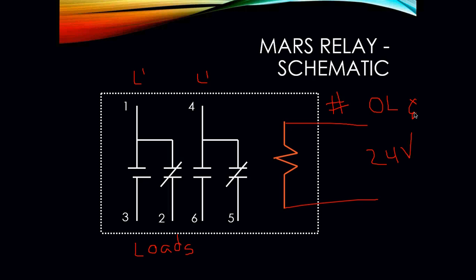Now let's look at it from the switching side of it, the switches. Terminals 1 and 3, that's normally open. Remember, when it's in its de-energized state, this is open. So I should read on my meter, OL. If I'm reading 0 across this and this coil is de-energized, it's telling me that this switch is actually welded closed. It's no good. Remember, normally open is when it's in a de-energized state. So I should be reading OL there.